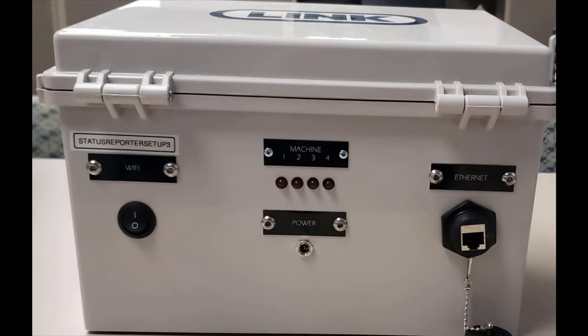To actually connect the module to your LabLINK installation, you will need to use the Ethernet port located on the right side of the module. You will also notice at the bottom center the power input. This requires a 5-volt adapter. And directly above that, we have LEDs that communicate machine status for up to 4 machines.